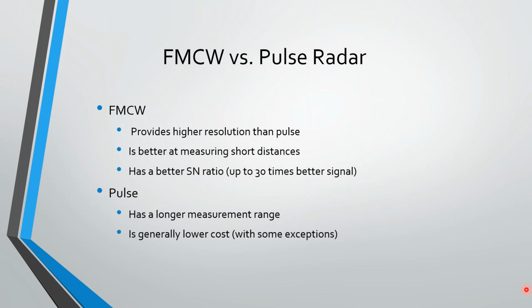FMCW provides the highest resolution. It's better at measuring short distances than pulse, and has a better signal to noise ratio than pulse, up to 30 times better. Pulse does have a longer measurement range. That's kind of arbitrary though, because FMCW can go a pretty fair distance as well. Pulse is generally lower in cost, but I'm not sure that that's 100% true anymore. When FMCW devices first came onto the market, they were more expensive than the pulse radar devices, but in recent years, they've pretty much balanced out. So again, they're getting closer and closer in price, and FMCW gives you much better performance. So even if it was a couple dollars more, it would be worth it.